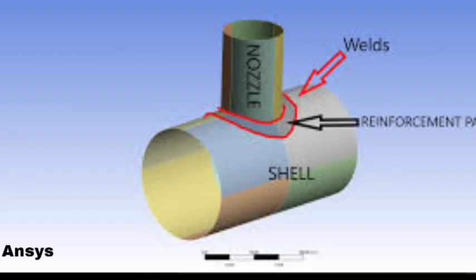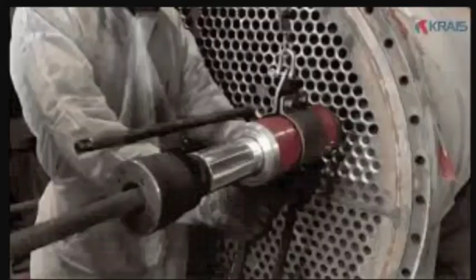So I mean to say this 1.5 times criteria is standard. There is no single 1.5 times standard for all tapping things, like pulling eyebolts - sometimes pulling eyebolts and tie rods are diagonally opposite on the tube sheet faces, one on the shell side and one on the tube side. So we change the location of the tie rod or pulling eyebolts. Okay.